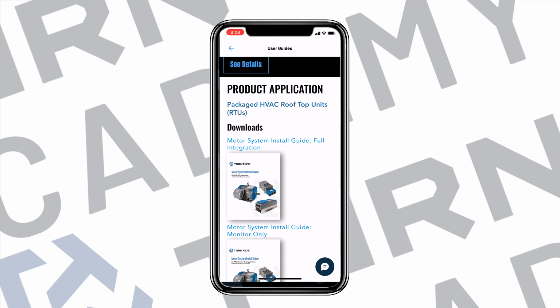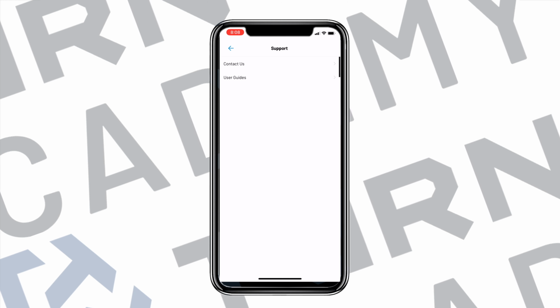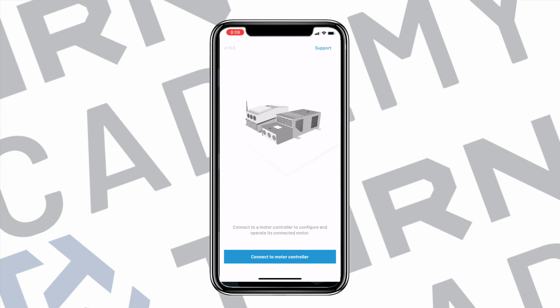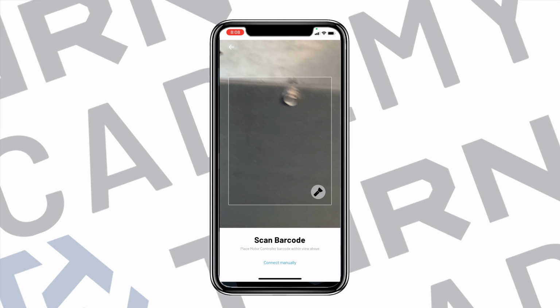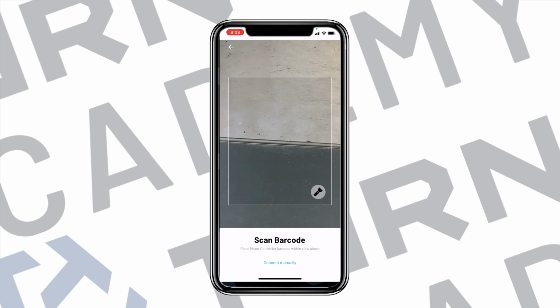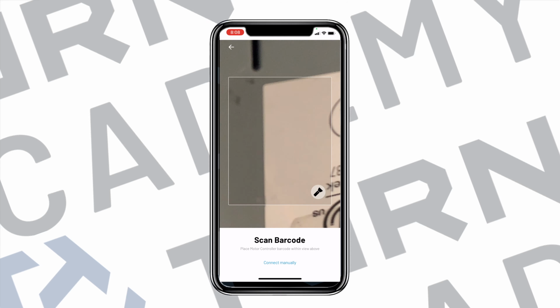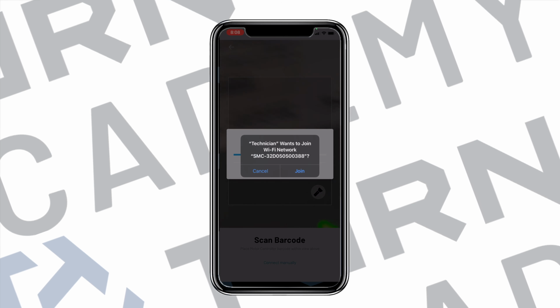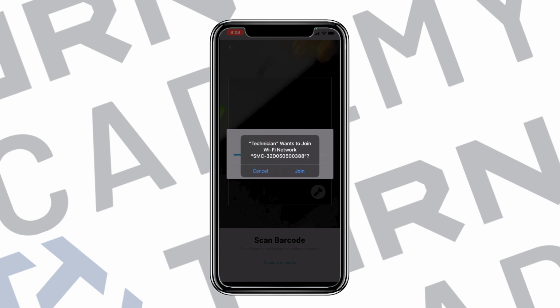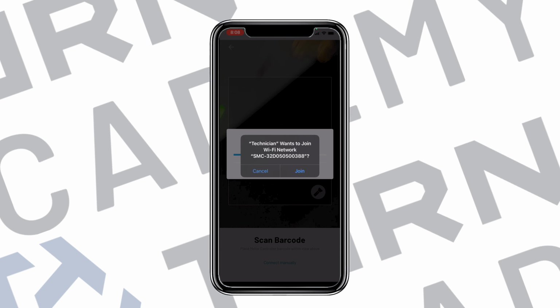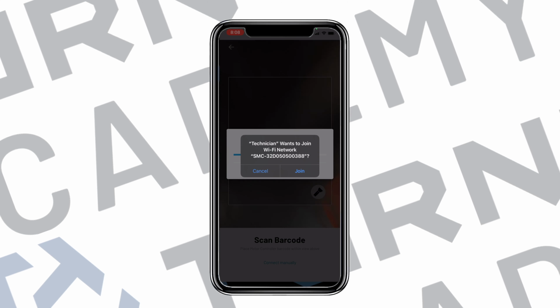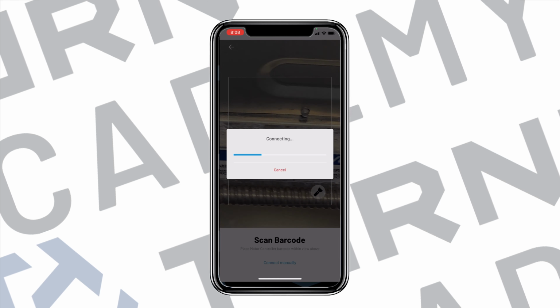The first step in the commissioning process is to configure the motor controller. Start by touching the Connect to Motor Controller button and scanning the motor controller barcode. The motor controller emits a localized Wi-Fi signal to enable wireless connection between the motor controller and the smart device. Touch Join to connect to the motor controller.